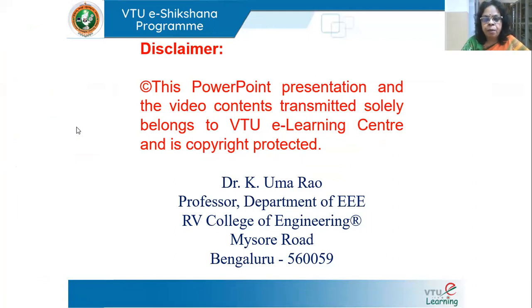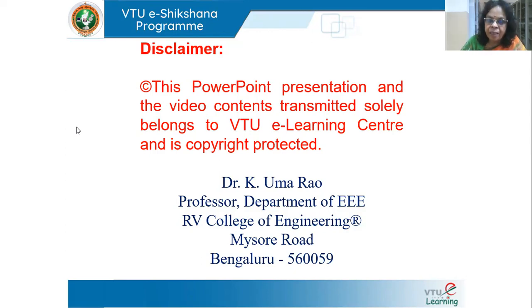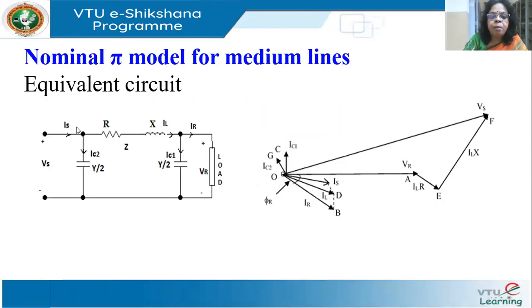In my last session, I detailed about the T model for medium lines. Medium lines are between 100 to 250 kilometers, and this is basically how we model the line. In the short line, we neglect the capacitance, and in the medium line, we have to consider it because this capacitance will have a significant impact on determining the efficiency and regulation of the line. In this class, we will see one more model which is called the pi model.